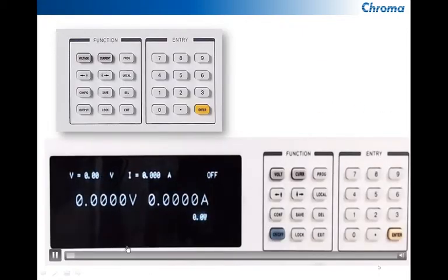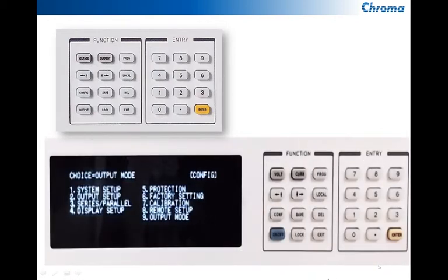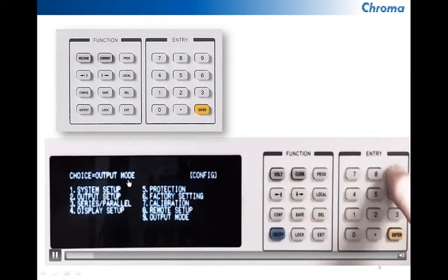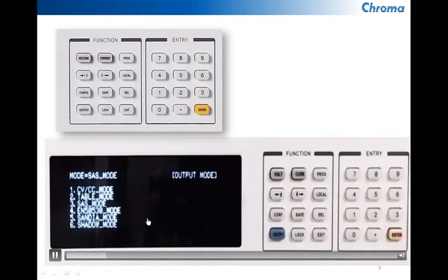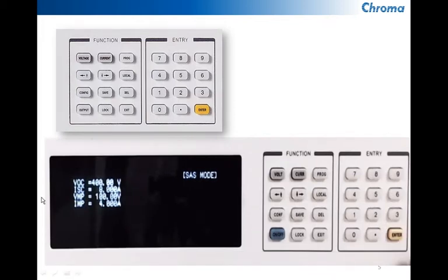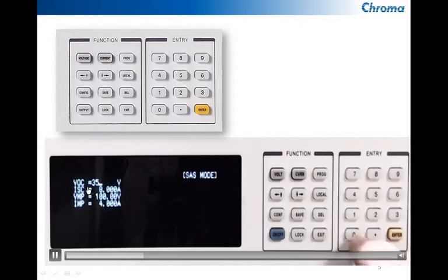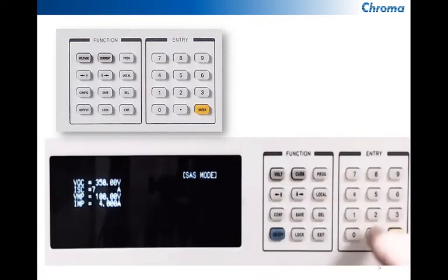I've started a video running here that'll show you a live demonstration of this unit. What we have here is the configuration or choice output mode and with that you can select 9 which is the output mode settings. There's also a selection for solar array simulation. When you select solar array simulation mode it's going to give you the ability to input these different parameters for open circuit voltage. We'll set that to 350. We're going to set the short circuit current to a maximum of 7.5 amps, and then we're going to set the maximum voltage setting for maximum power to 300 volts.